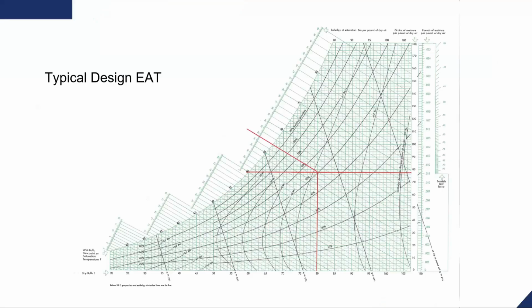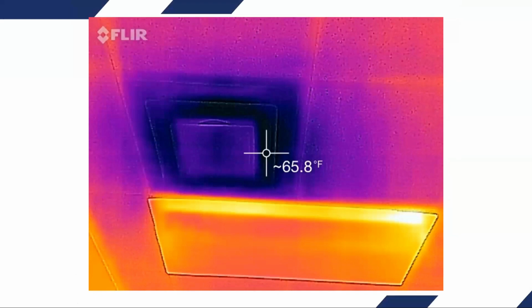So around here, at least, our design entering air temperature conditions are 80 and 67. So 67 degree wet bulb, 80 degree dry bulb. I've just represented this on a psychrometric chart so you can see, if we've got those design conditions, dew point needs to be at least 60 degrees. So we need at least 60 degrees leaving those units in order to remove the moisture. Again, I have a thermal scan of a diffuser, and believe me, I understand that that 65.8 degrees that's showing there doesn't necessarily represent the air temperature. That's the surface temperature of the grill. But we did take actual readings of the equipment, and this is with the piece of equipment operating under normal circumstances, which was in first stage. We were nowhere near what we needed to get to achieve that dew point temperature leaving the unit.